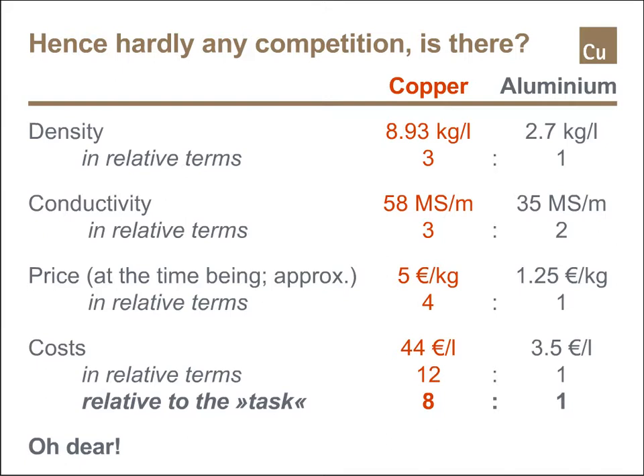you end up with a ratio of 8:1. Actually, you cannot compare the same mass or weight to compare the quantities of the metals, but you must compare the volumes, because the cross-section is decisive. And on top of the cross-section, you have to compare the conductivity. Conductivity is only 2/3 for aluminium, so you have to multiply the cross-section by 3 divided by 2, and then you arrive at a factor of 8 for the price that you have to pay for an equivalent conductor.